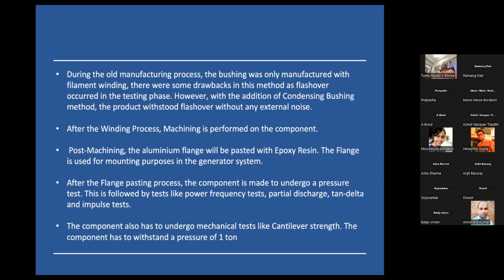When we were initially manufacturing generator bushings, in the old process, we only used filament winding. This had some drawbacks, as we used to get flashover during the testing phase. So when we went back and redesigned the generator bushing, we added an additional method called the condenser bushing. With the condenser bushing added along with the regular filament winding, the product would not flash over, without any external vibration or noise. So that's why we do the additional condenser bushing method.